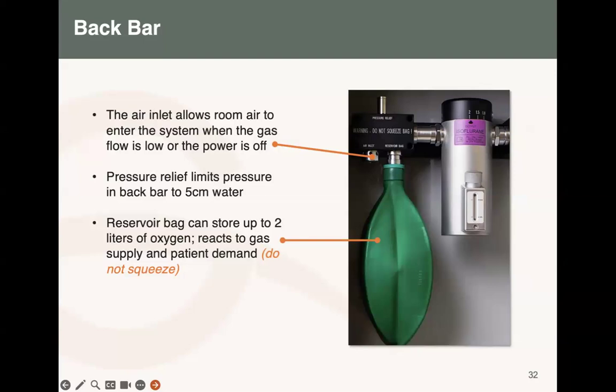Here is where the reservoir bag is attached. The reservoir bag is meant for reserving oxygen, so that the machine can draw oxygen from here when giving it to the patient. It can also help you in monitoring the patient. When your minute ventilation matches the fresh gas flow, this should be half filled. The moment this collapses, you should know the minute ventilation is higher than the fresh gas flow. That means the oxygen you are providing is less than what you are targeting, and by then the machine will draw air in.